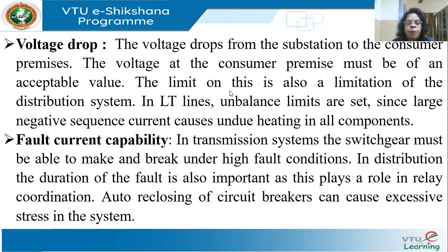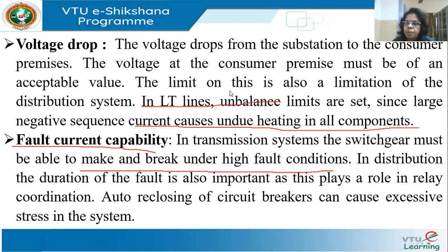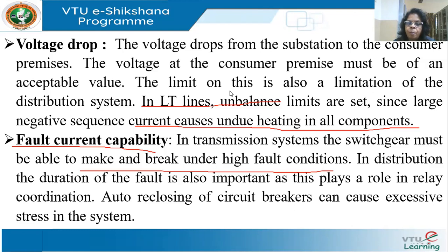Depending on your application you set the maximum permissible voltage limit. If there is unbalanced loading, it causes further problems due to undue heating, as the negative sequence components cause excessive heating. Fault current capability is also important — until breakers or fuses operate, the lines must carry the fault current. The switchgear must be able to make and break under high fault conditions. When you have a number of protective relays, coordination between the time of operation also depends on the fault levels.